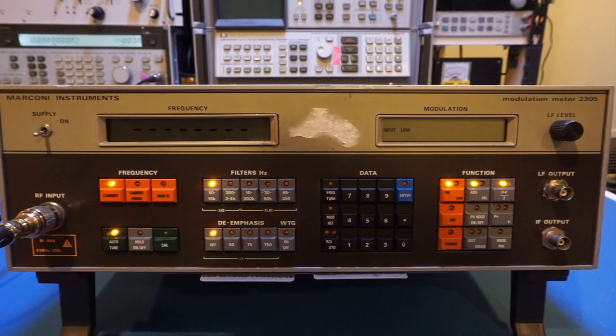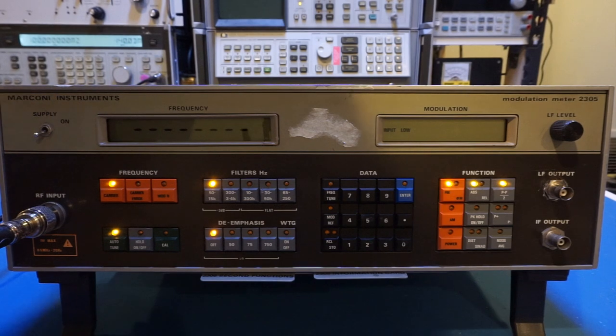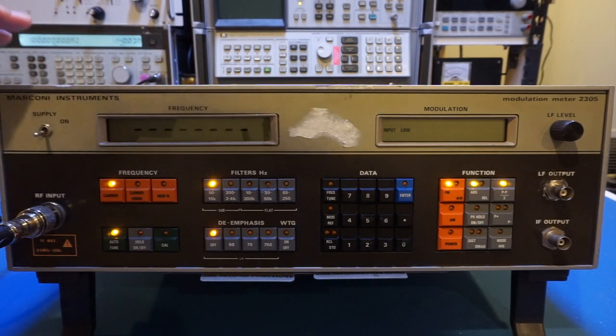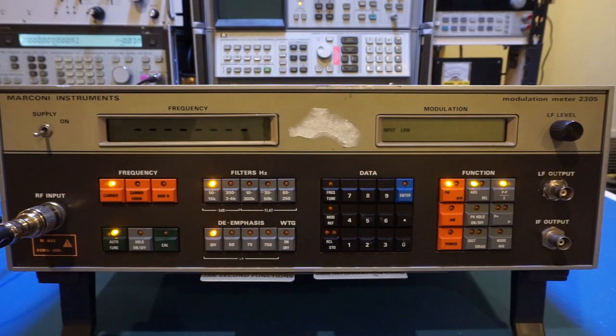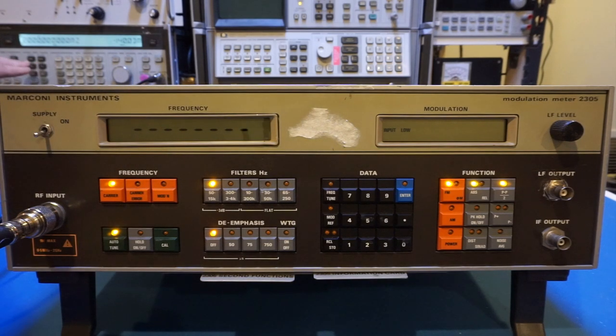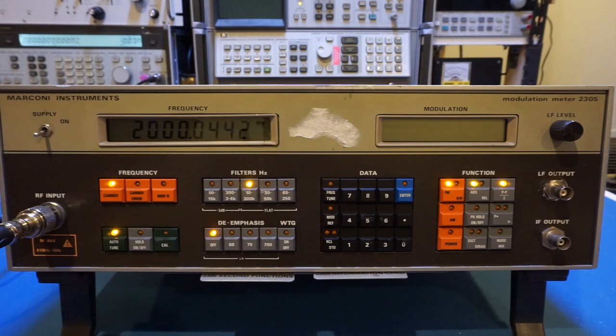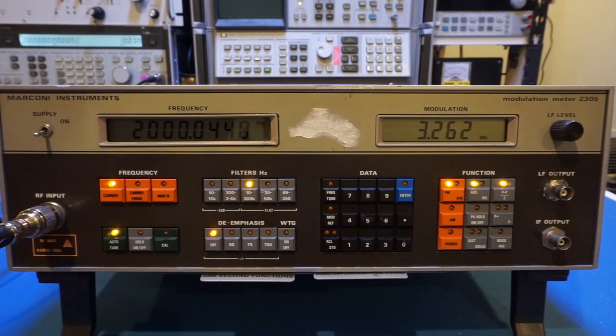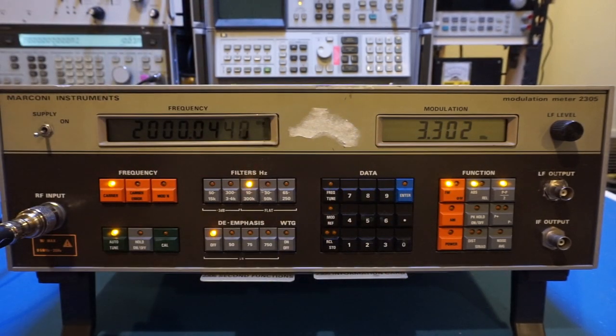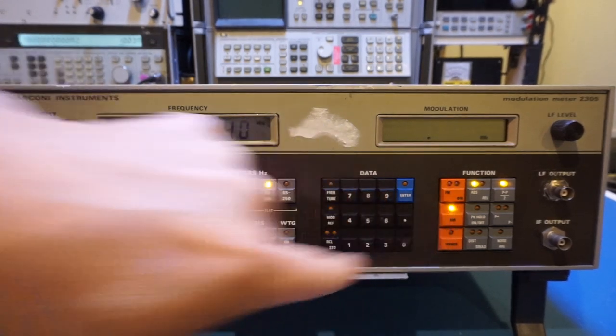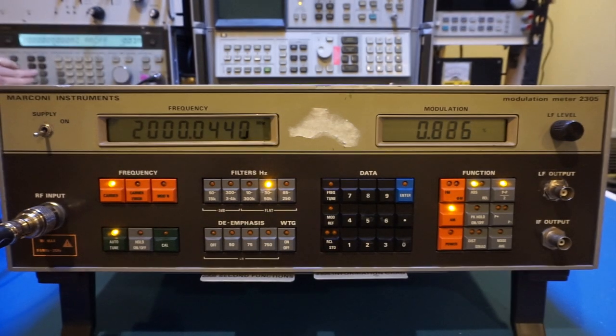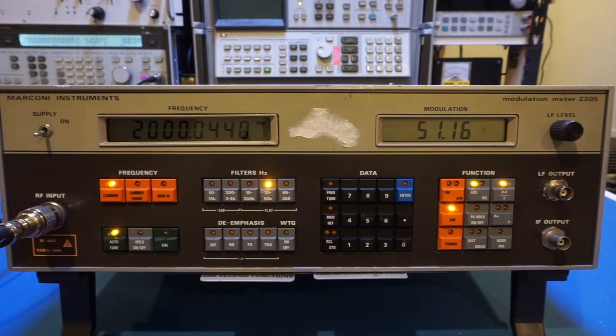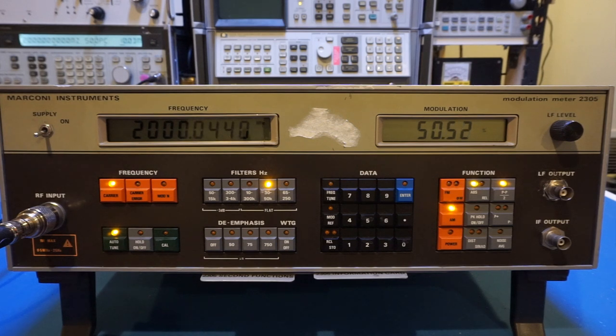To test it briefly, I just powered up my HP 8642B. I'm going to set the frequency to two gigahertz, which is the upper limit of this Marconi 2305. I'm going to set the output to roughly 10 dBm. As you can see, we can indeed see the frequency here showing two gigahertz. Right now we're showing this is actually for FM. Let's just do a quick AM modulation just to first sanity check here. Now it's not modulated, so it's showing zero. I'm going to turn on the AM modulation. Right now it's set to 50%. As you can see that indeed it's around 50%. I think this is now a functioning meter.